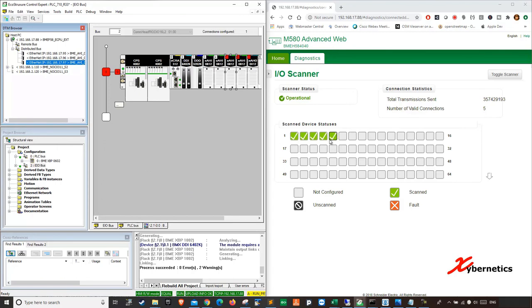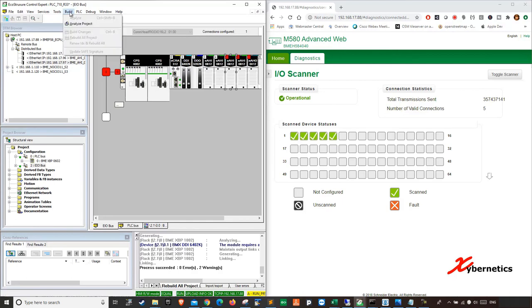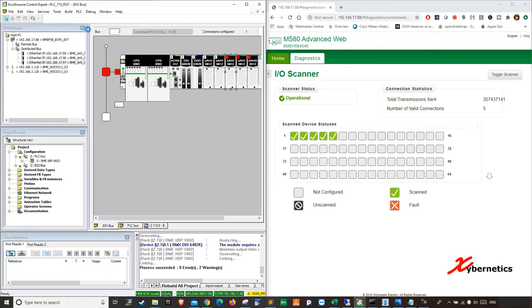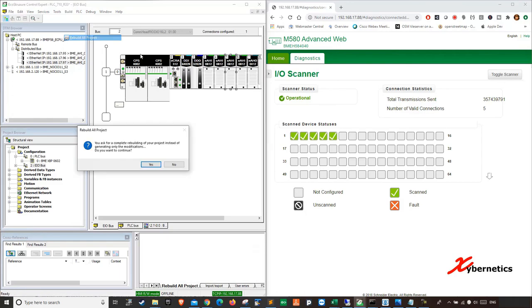You still have to build the configuration on the side, but let's try this way. If you right click this, device menu, additional function, transfer to FDR. So you are basically transferring all the configuration back. So the configuration was successfully transferred. And now your checkbox is good. But right now what happened here is that you still have to do an overall compile and download because this thing will not go away until you do that. So you go build, disconnect yourself here and then go build, rebuild all.